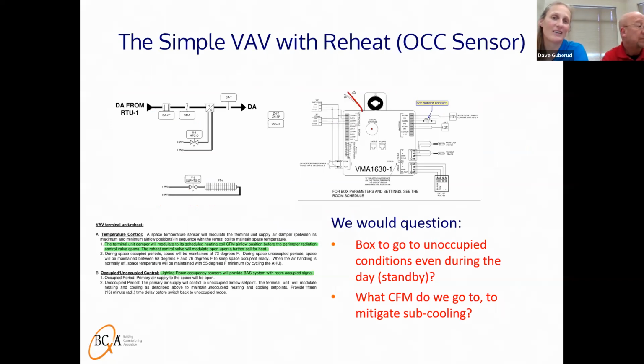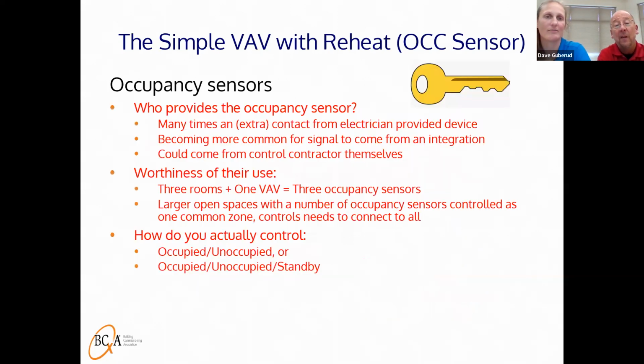Occupancy sensors. So understanding, with an occupancy sensor, that it is provided by whom. And if a box goes into unoccupied conditions during the day, which we would call standby, so the room is typically in occupied mode and it goes unoccupied, understanding that versus evening times. What CFM do we go to to mitigate subcooling? So just kind of talking through the different sequences and the different processes so that we're all understanding things the same way. And I guess the next thing on the occupancy sensor, it's on the next slide, right, is the occupancy sensor itself.